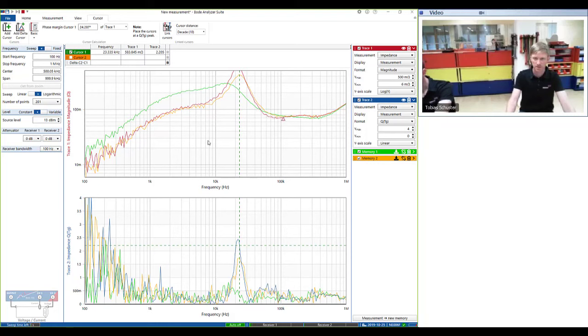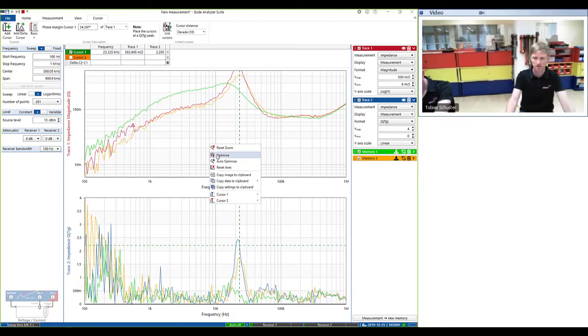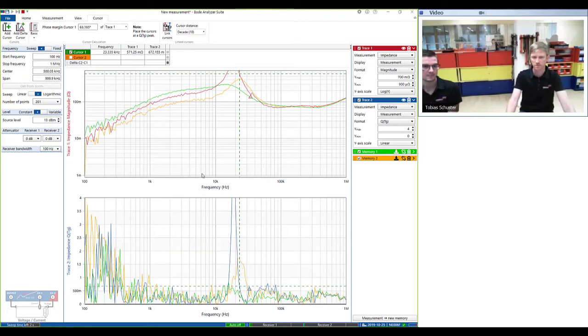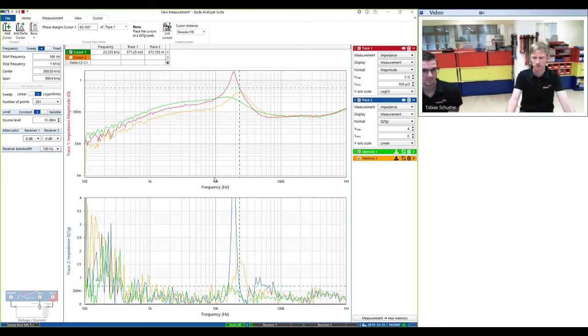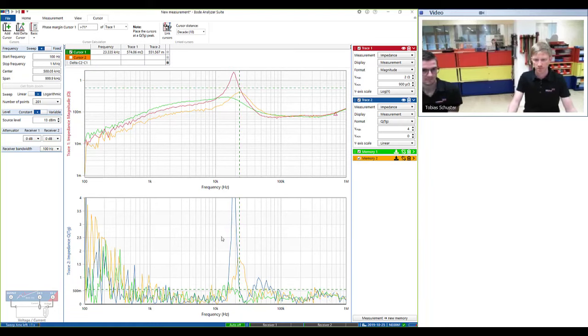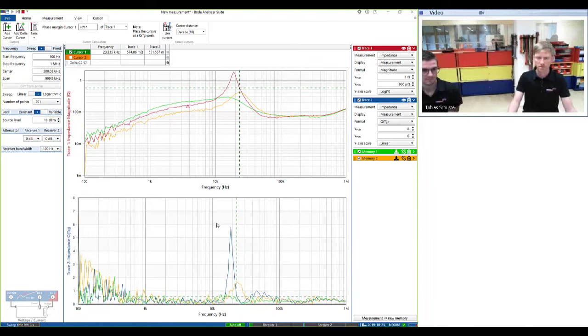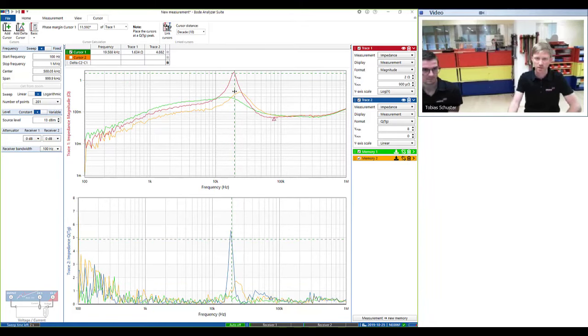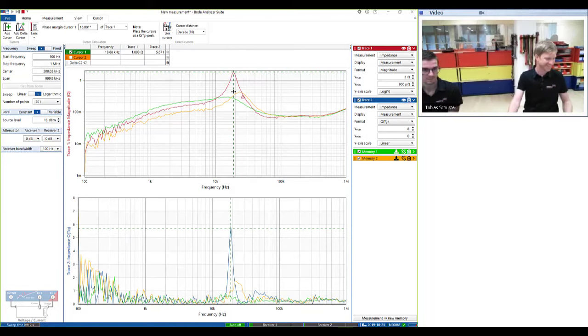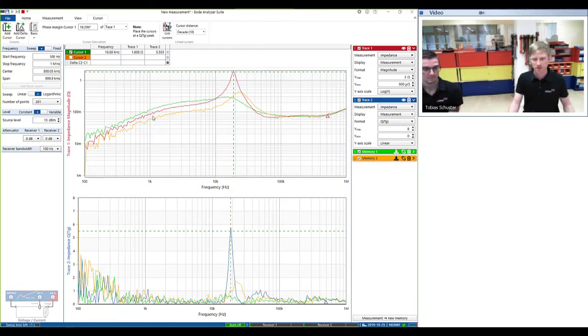Tobias, can you please lower? So the input voltage is now at 20 volts. Okay. So now the peak in the Q has gone very high. Also the peak in the impedance is now very high. We can see a peak in impedance up to nearly 1.6 or 1.7 ohms, so nearly 2 ohms of impedance at 20 kilohertz, which is not a really good supply in that case.